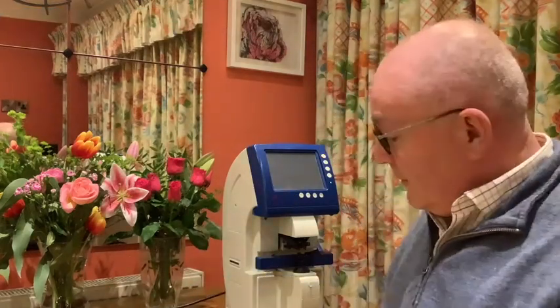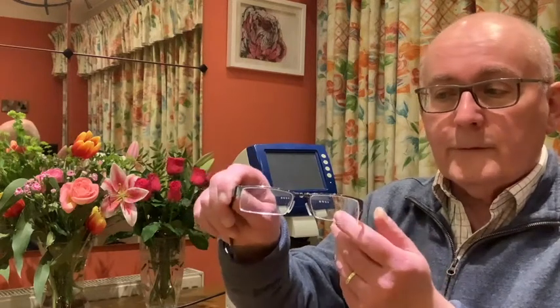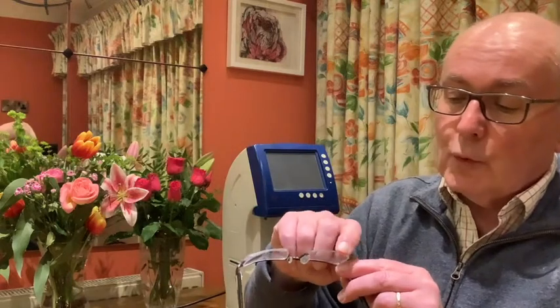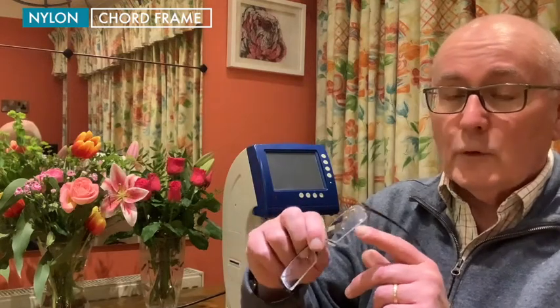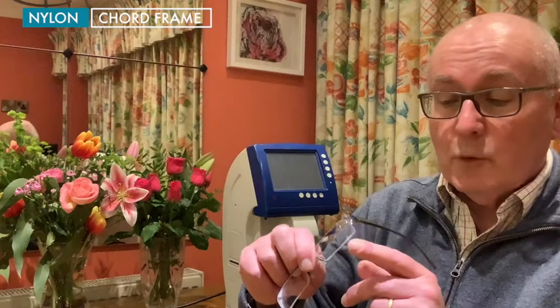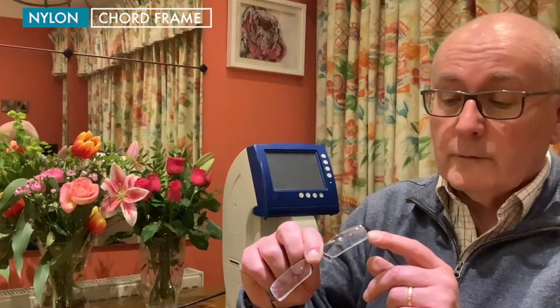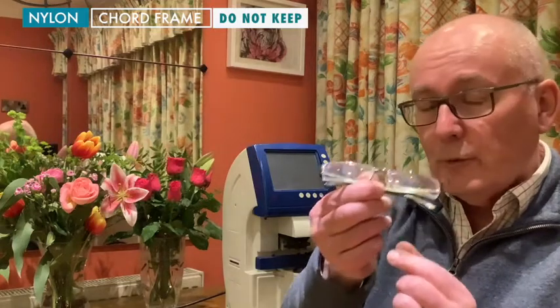Now the kind of things we don't want to keep. To start with, this type of frame where you'll notice there's apparently no rim at the bottom. In actual fact there is a nylon cord running around the bottom of the frame, and the issue is that the nylon cord may perish — especially in hot, moist climates. If the nylon fails, then the lens is going to drop out. So we ask you to discard any Supra lenses.